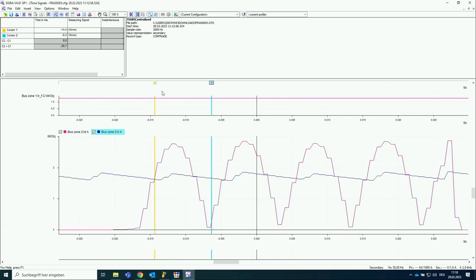And after the state time of 8 milliseconds, we will have a measurement window of 6 milliseconds. Within the 6 milliseconds, we need 4 threshold exceedings. You can see at the very beginning, when the measurement window is opened again, we will have no threshold exceedings. So it starts here. Beginning from this moment, we will have threshold exceedings again, and then we need 4. I think that could be quite fine, so that really at the tripping time, 4 threshold exceedings should be possible.